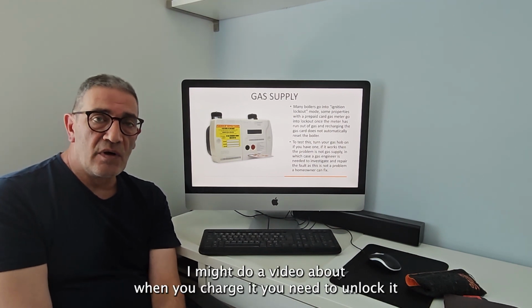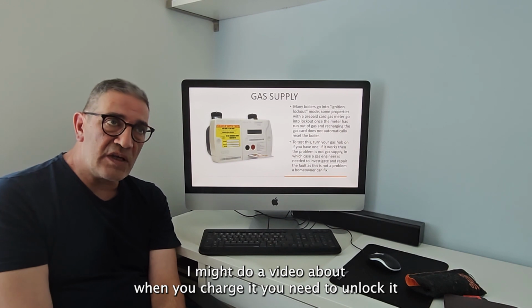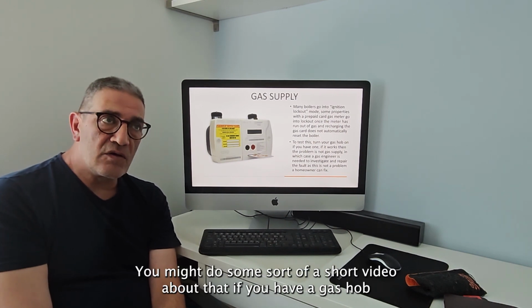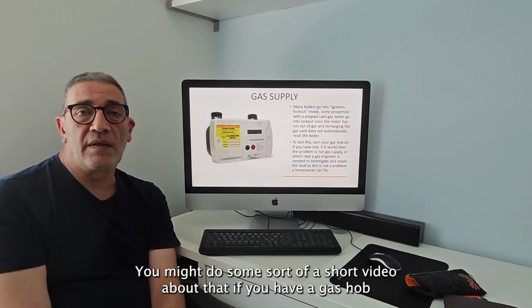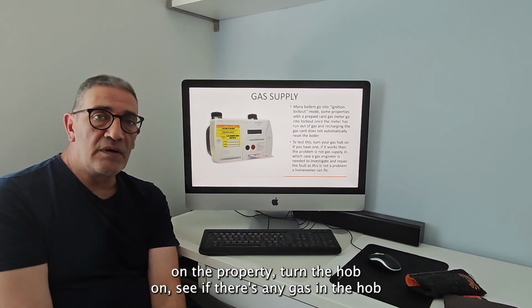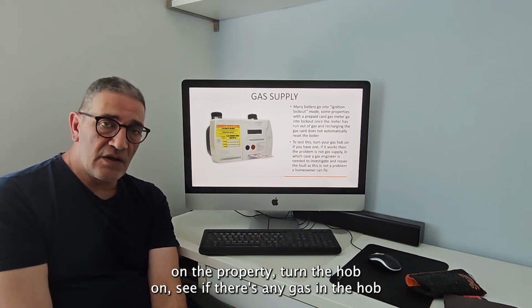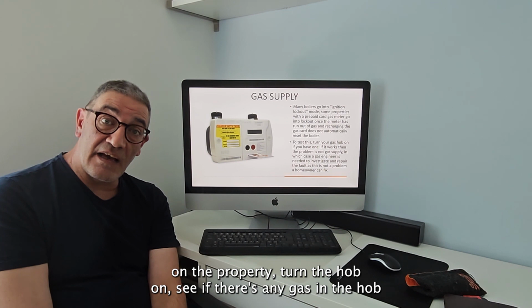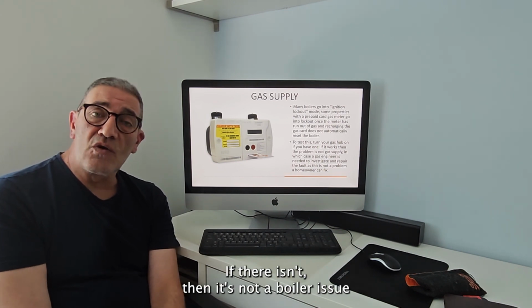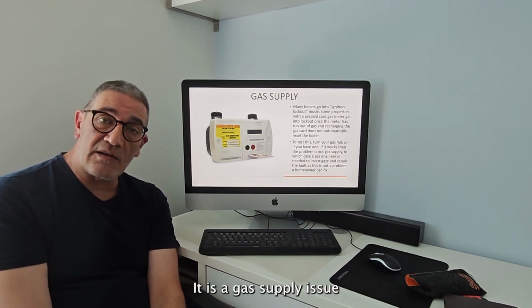I might do a video about when you charge it, you need to unlock it. You might do some sort of short video about that. If you have a gas hob on the property, turn the hob on, see if there is any gas in the hob. If there isn't, then it's not a boiler issue, it is a gas supply issue.